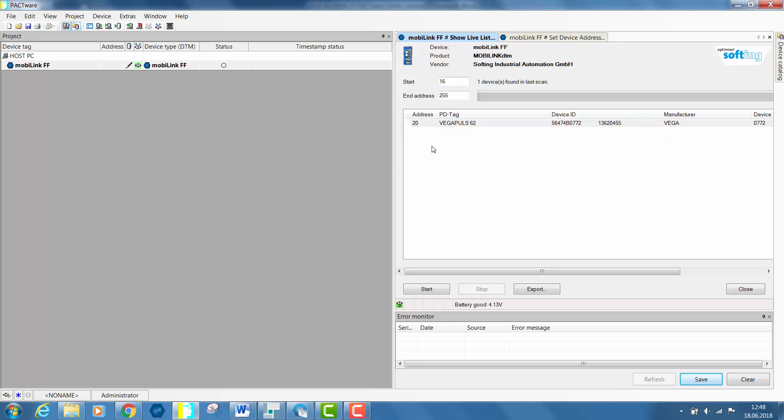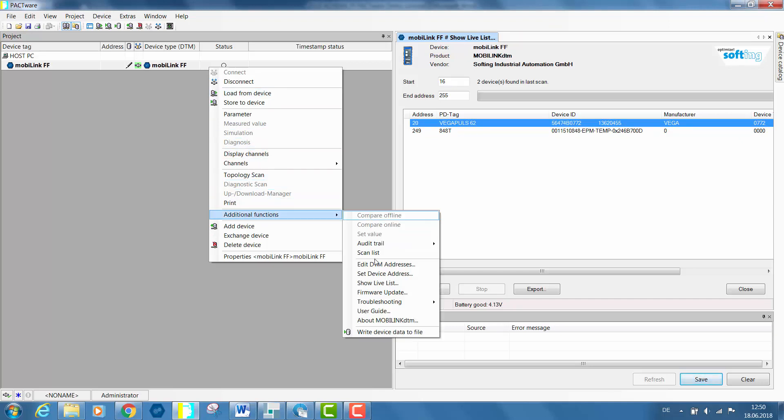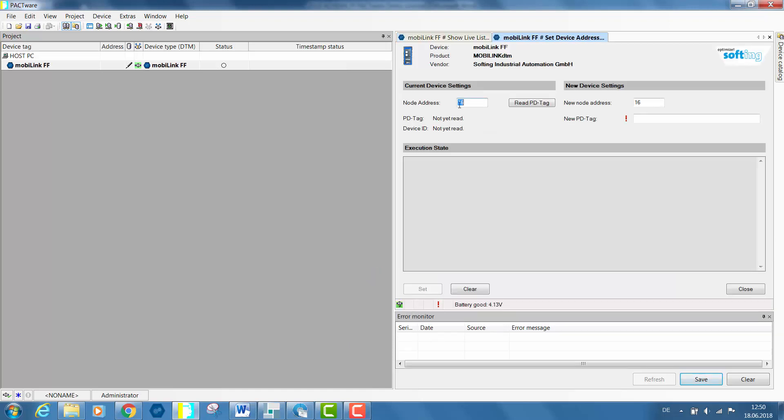Now, the goal is to modify this node address to the range of node addresses for permanent devices from 16 to 247. Right click on the MobiLink FF DTM. Go to Additional Functions and select Set Device Address.